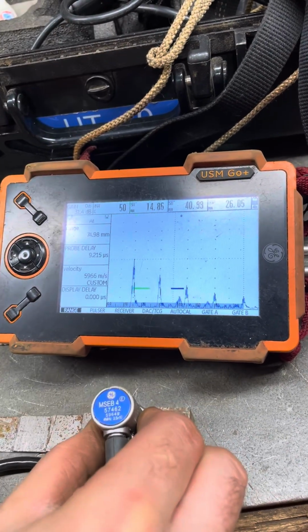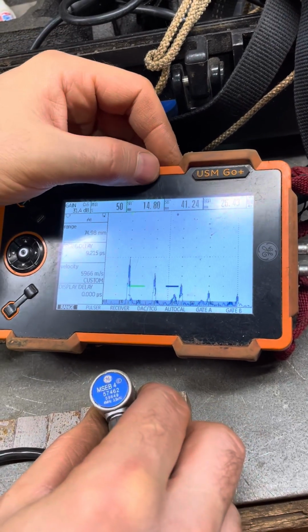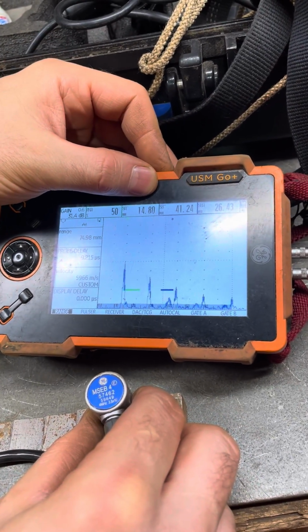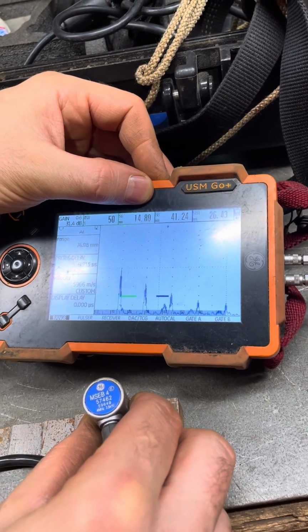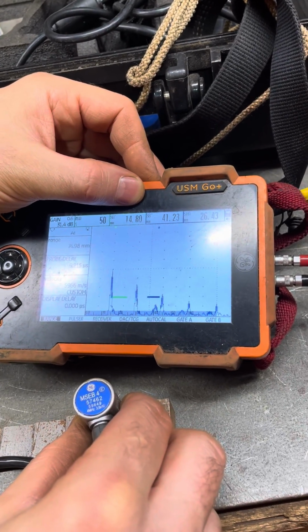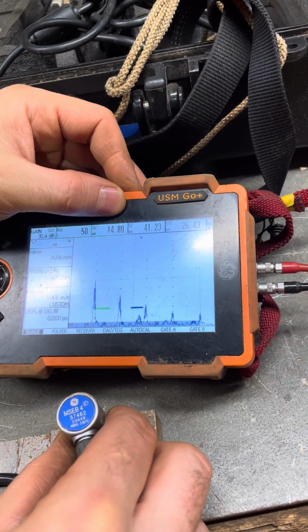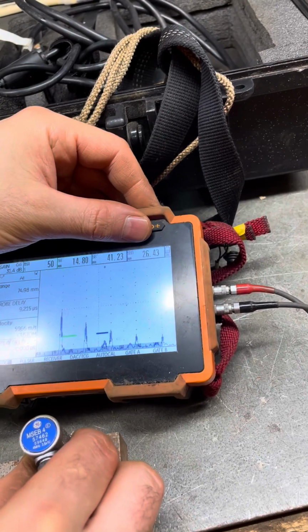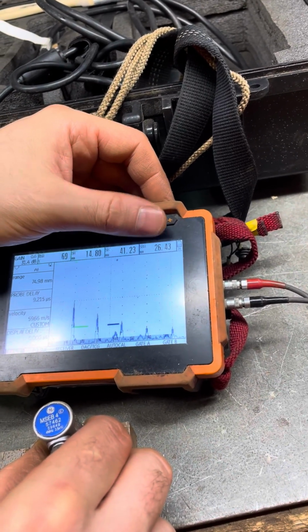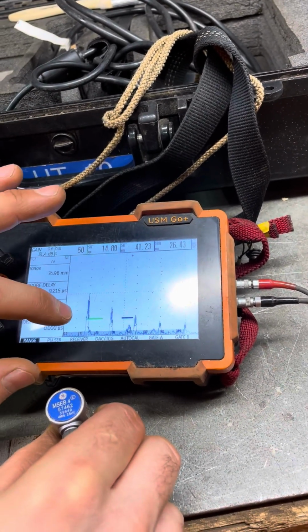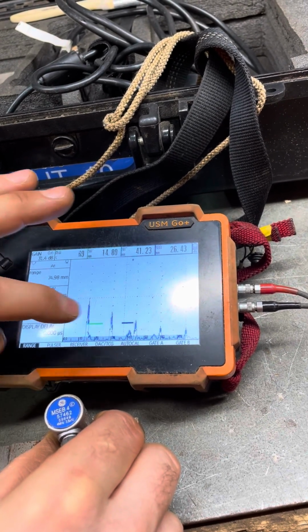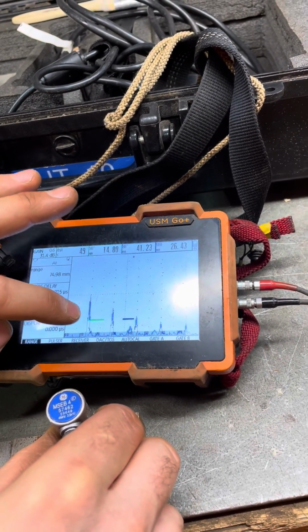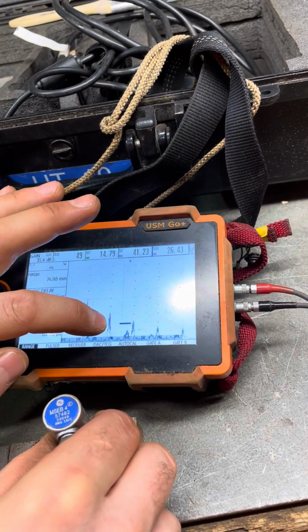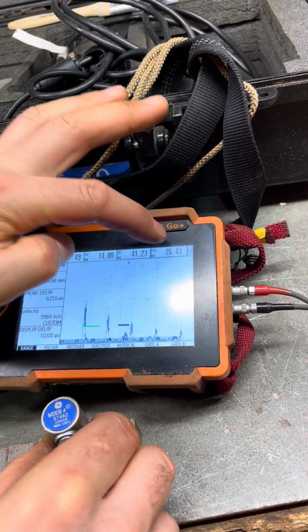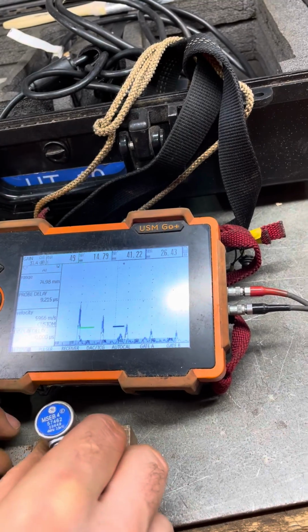And it already shows us that the device is set to 14.8. It needs to be calibrated, and it needs to be adjusted to 15, right? Now let's see, without paint, it comes out to 26.43. That's incorrect, it's showing the wrong value because we need the first gate to be green, specifically green, not blue. You mustn't mix them up. Gate 1 should hit the first signal, gate 2 should hit the second signal, then it will display correctly for us. Ours is offset. That's what it turns out to be, yes?